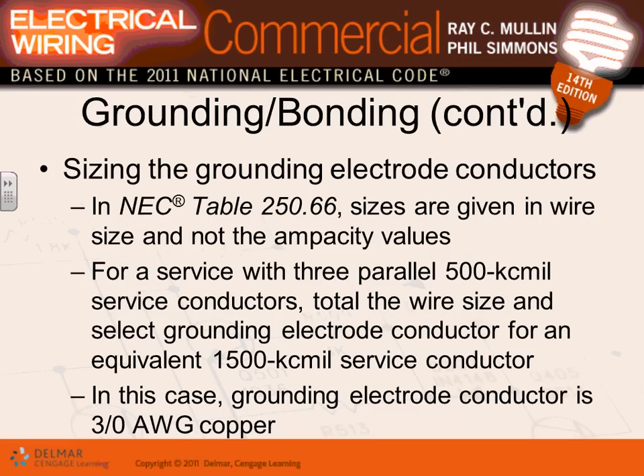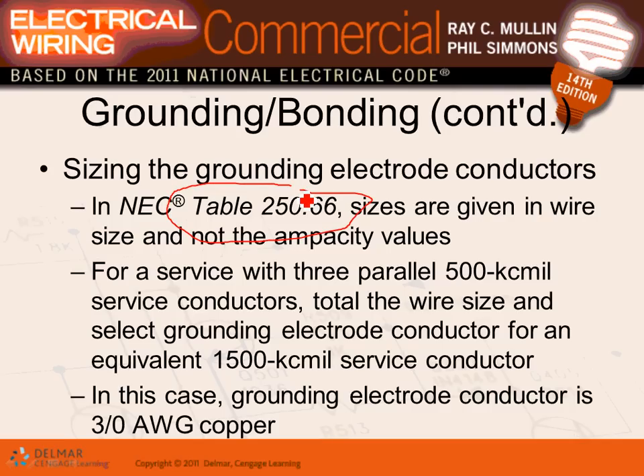Now, sizing the grounding electrode conductor. When we size it, we use table 250.66. You have sized the grounding electrode conductor for me in your load calculation. You take the service conductors coming to the building and you size it. Here's an example in a commercial project. They're using 3 sets of 500 kcmil conductors in parallel. When you multiply 3 by 500, what do you get? You get 1500. Then you take the 1500 to table 250.66, which you did for me when we did the load calculation, and guess what you get? You get a 3/0 conductor that you tie to your water system.